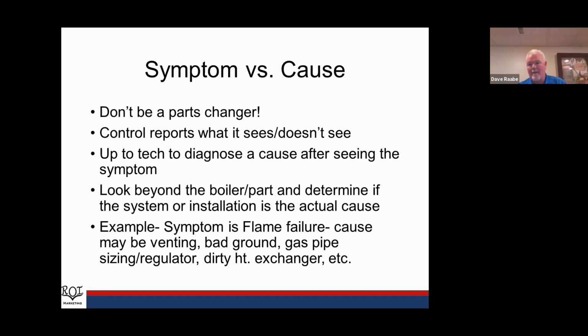And remember that boilers are a small part of a heating system. When they're locked out, it's easy for a customer to blame the equipment, but it could be something beyond that. It could be the installation. It could be something in the system causing the problem. So we really need to look beyond the boiler or part and determine what's causing the problem. So I threw an example on here, and one of the most common things we could run into on a boiler is flame failure. So what could cause flame failure?